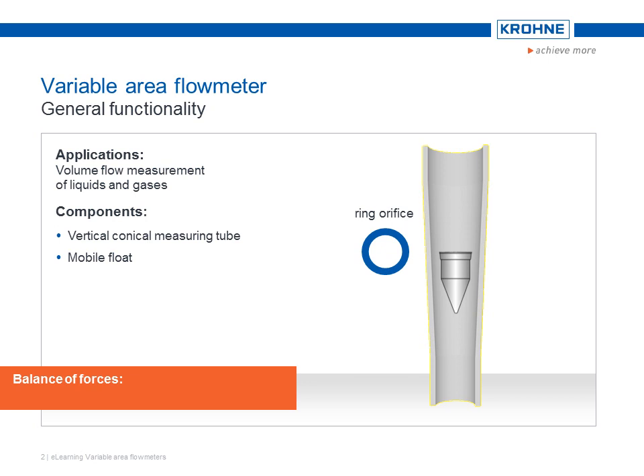Three main forces act on the moveable float. The gravitational force W, weight, operates downwards as the reset force. Whereas the buoyancy force B and the flow force D, drag, work in an upward direction.